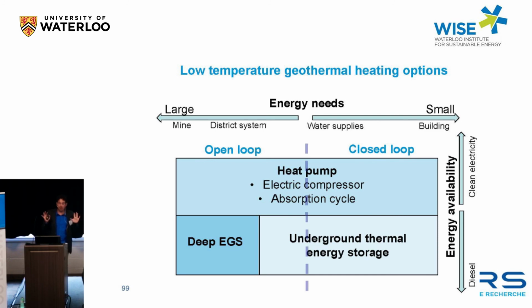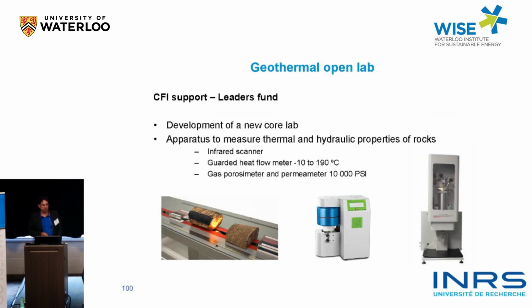So this is what I believe are the low temperature geothermal heating options in the north according to energy needs and energy availability. For large needs, open loop systems are better suited because they have higher capacity, but they tend to be more demanding on maintenance. So closed loop are better suited for smaller applications. Heat pumps, when there is clean electricity, are viable options, especially heat pumps with an electric compressor. When there's no electricity, it goes to the absorption cycle. And then, as a long-term goal, EGS systems and underground thermal energy storage could produce 100% renewable energy.